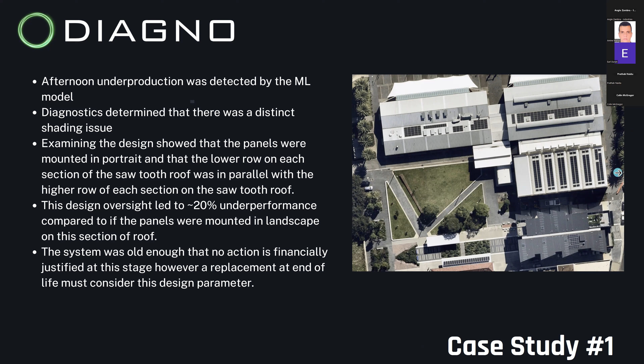So this is actually a design issue. The system in this case was old enough that no action was financially justified, because you'd basically have to remove that whole part of the array and twist it 90 degrees. However, at replacement, you'd want to consider that design implication for the next system. It's quite an interesting result, because no action is recommended, but this is very powerful information for the customer, who can take it into the next phase of solar on this roof.